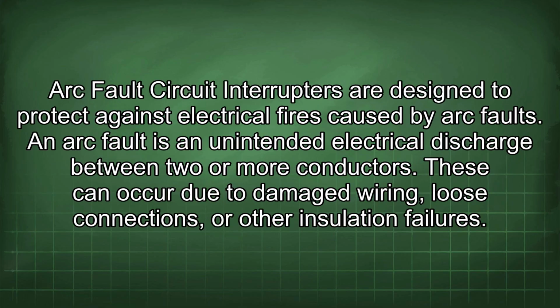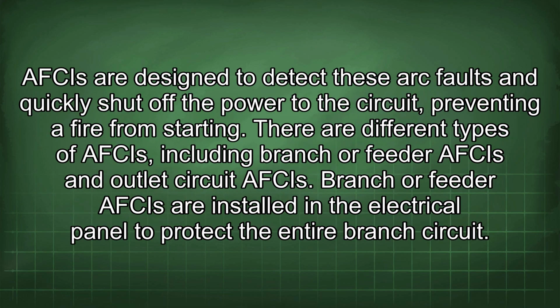Arc fault circuit interrupters are designed to protect against electrical fires caused by arc faults. An arc fault is an unintended electrical discharge between two or more conductors. These can occur due to damaged wiring, loose connections, or other insulation failures. AFCIs are designed to detect these arc faults and quickly shut off the power to the circuit, preventing a fire from starting.